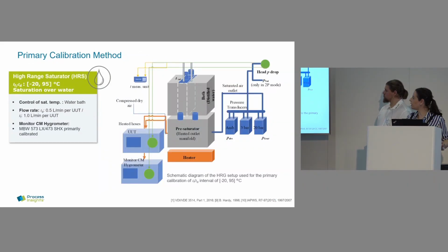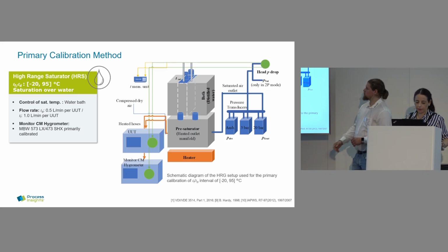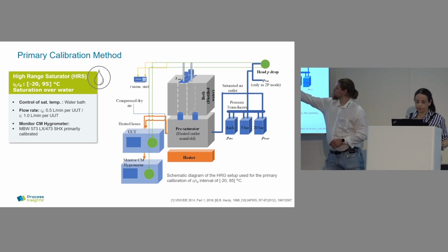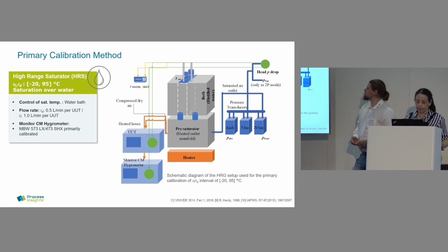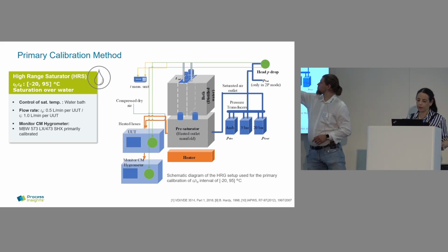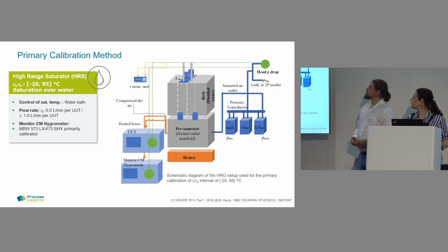Okay, so this time the saturator is inside the bath. It's not an ethanol bath, it's a water bath because of the temperature range. And below we have a pre-saturator that is programmed to be 5 degrees Celsius higher than the desired temperature. Then again, we need to measure the temperature of the saturator. Then we also have 1 PRT crossing the saturator, and another one in the bath for control.